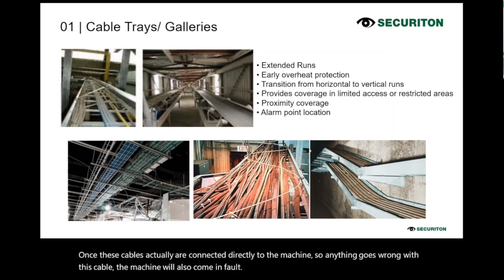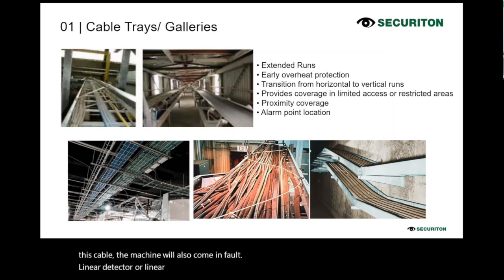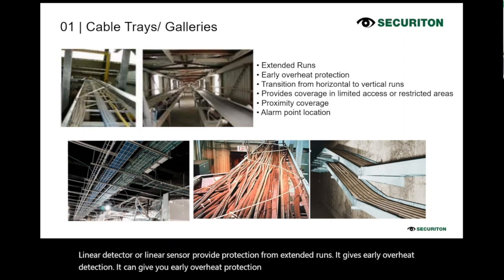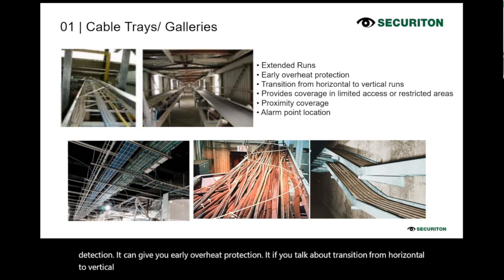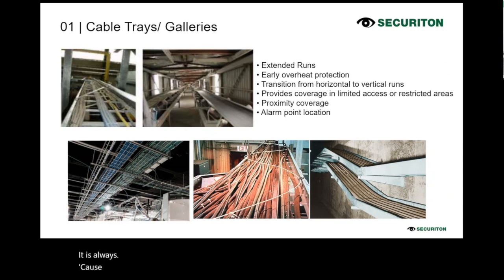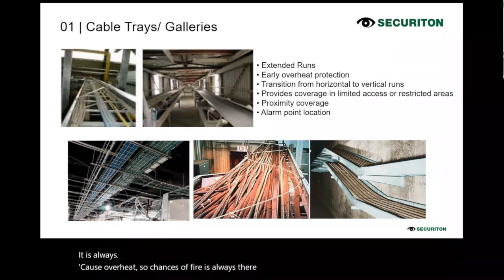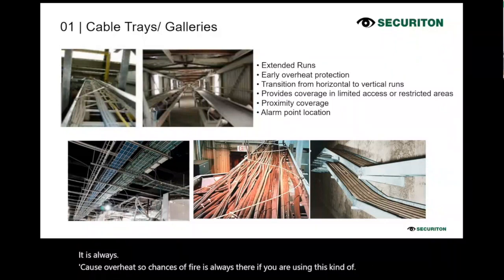A linear heat detector or linear heat sensor provides protection for extended runs. It gives early overheat detection and early overheat protection. The transition from horizontal to vertical run is a cable management system with a lot of pros and cons in both types. It can always cause overheat, so the chances of fire are always there if you are using this kind of management system.